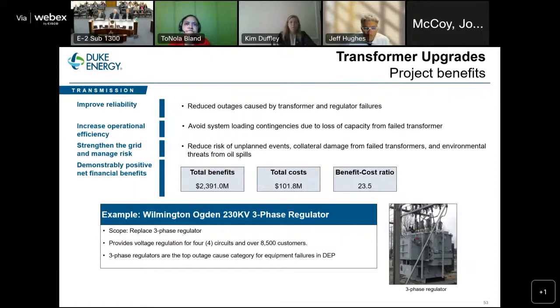The specific example or project location I'll speak to for our transformer upgrade project is the Wilmington Ogden 230 kV three-phase regulator replacement. This is in the Wilmington, North Carolina area. We are replacing a three-phase station regulator. This one regulator provides voltage control for 4 different distribution circuits leaving that station. Those circuits serve over 8,500 customers.